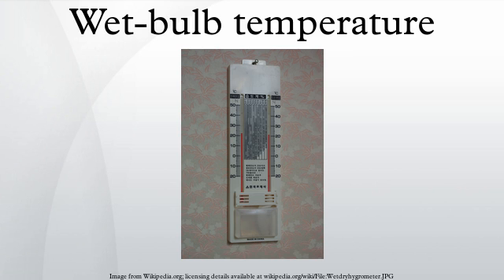Experimentally, the wet bulb thermometer reads closest to the thermodynamic wet bulb temperature when the sock is shielded from radiant heat exchange with its surroundings, air flows past the sock quickly enough to prevent evaporated moisture from affecting evaporation from the sock, and the water supplied to the sock is at the same temperature as the thermodynamic wet bulb temperature of the air. In practice, the value reported by a wet bulb thermometer differs slightly because the sock is not perfectly shielded from radiant heat exchange, airflow rate past the sock may be less than optimum, and the temperature of the water supplied to the sock is not controlled.